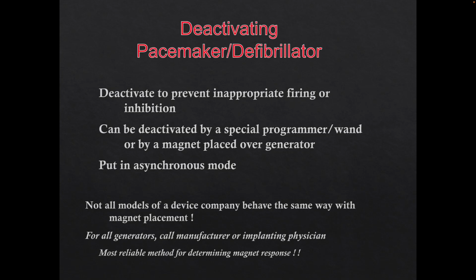The other thing you can do is when you go in, you can put them into asynchronous mode. When you put a magnet on, not each company is the same. They all respond differently. When you put a magnet on, it could do asynchronous. Like one company is 85. So when you put the magnet on, it'll start pacing at 85 DOO, if it's a dual chamber. If it's a single, VOO, if it's in the ventricle. All right. But usually you would want to call the manufacturer, call us, or whatever the case is, so we could determine what the response is going to be.